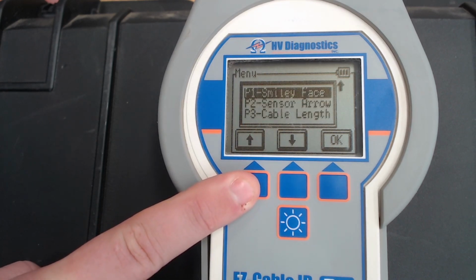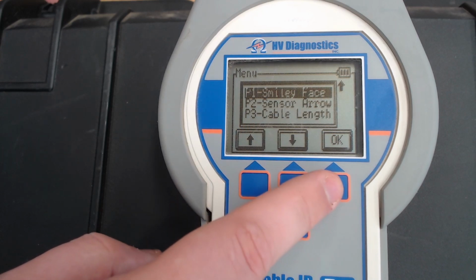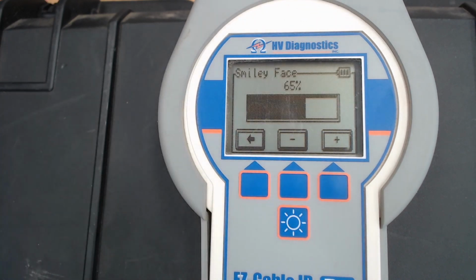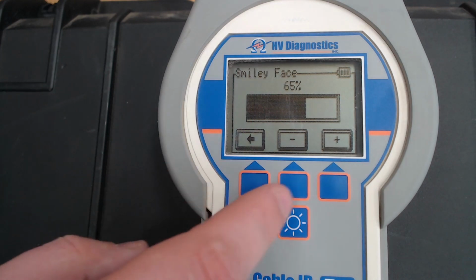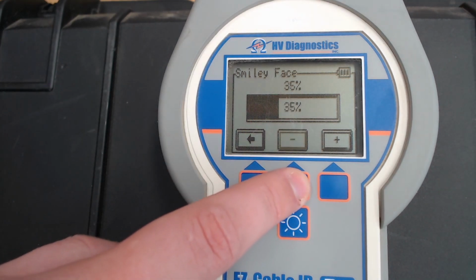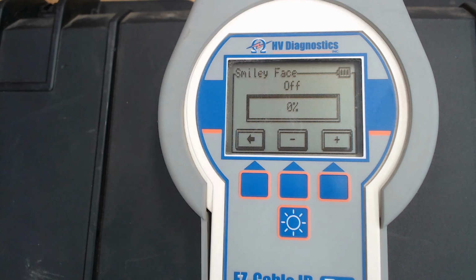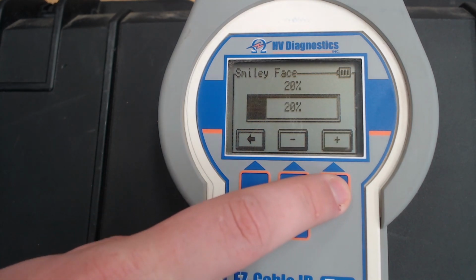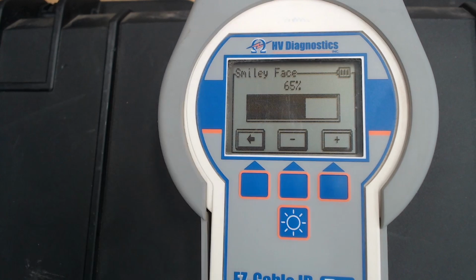So now let's go over the smiley face. The smiley face is our calibrated or uncalibrated mode. If I drop this smiley face all the way to 0%, so now it is off, we are in the non-calibrated mode. So if I turn on the unit, I hook up my test leads to my A phase, B phase, C phase, with my C being my return. I can just go straight out to the cable and start IDing. If I want to do a calibrated mode, I would turn the smiley face on. For our particular demo here, we use 65%.